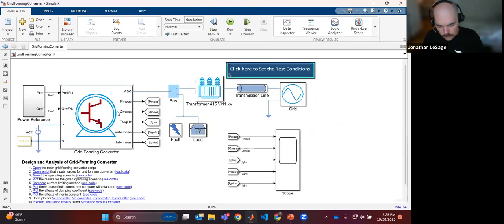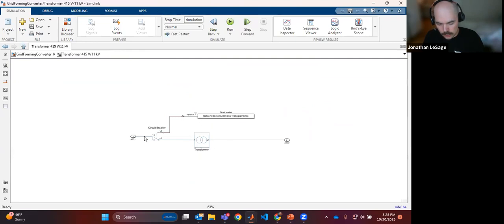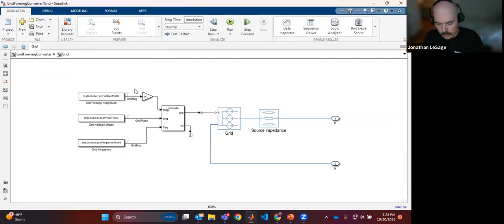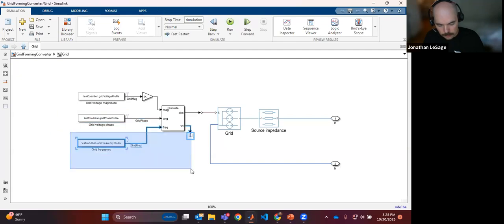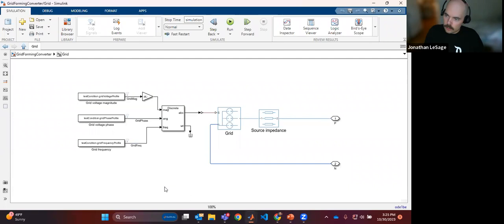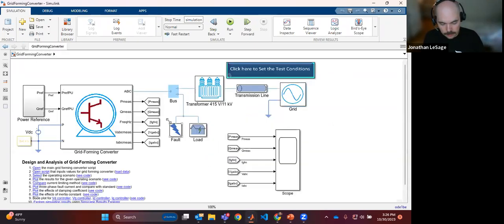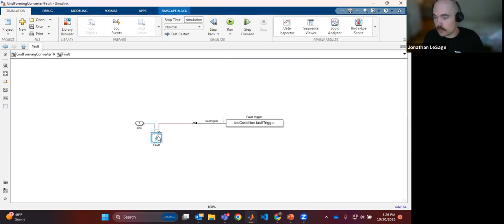Coming out of the grid forming converter, I've got a transformer, the ability to throw a breaker to simulate a fault, a transmission line model, and a connection into the grid. This allows me to feed in measured voltage profiles, phase profiles, and frequency profiles to simulate different scenarios — frequency changes, voltage changes, checking against specific grid codes — and there's also a fault block to do three-phase or single-phase faults to ground.